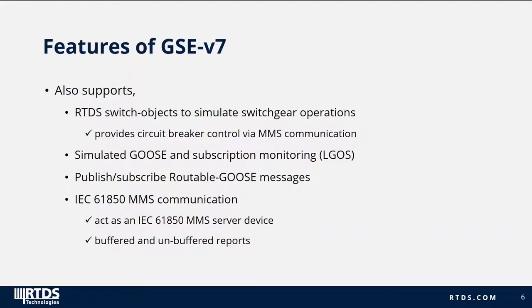The GSE V7 component can subscribe to up to 32 different GOOSE streams from external IEDs, and up to 512 data items in total. The GSE V7 component also supports RTDS switch objects to simulate switchgear operations, providing circuit breaker control via MMS communication. It also supports simulated GOOSE subscription monitoring — the LGOS feature described in the IEC 61850 standard — and supports publishing and subscribing routable GOOSE messages. For MMS communication, the GSE V7 component acts as an IEC 61850 MMS server device, supporting both buffered and unbuffered reports.